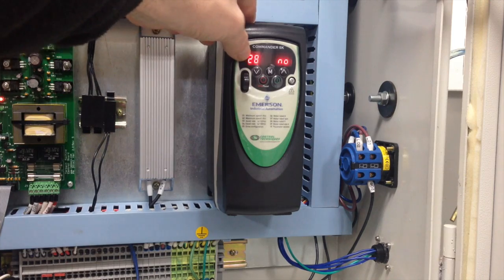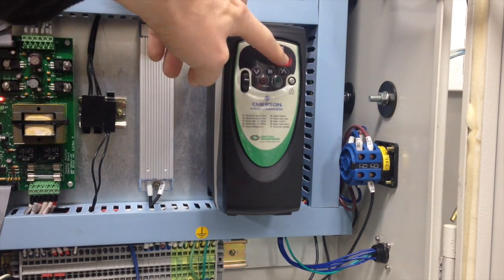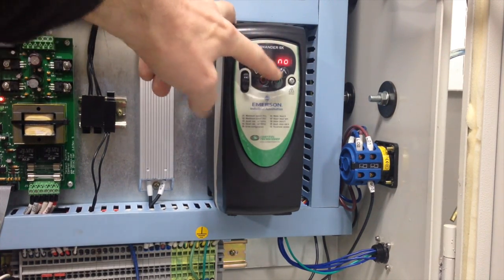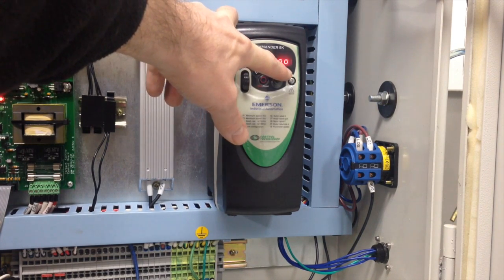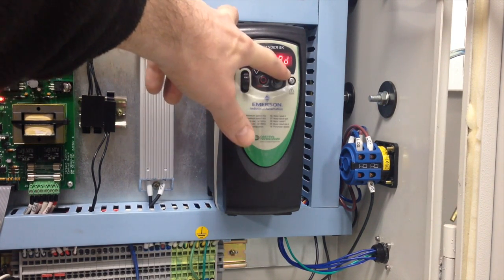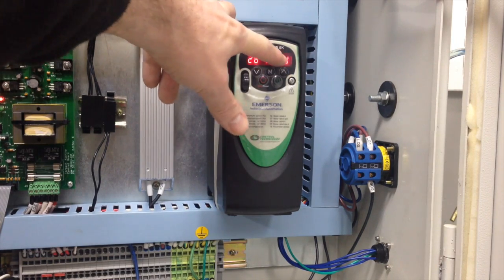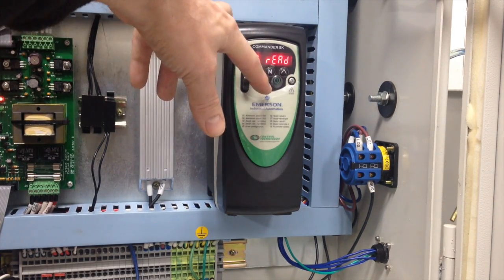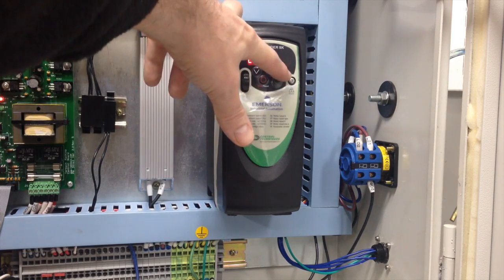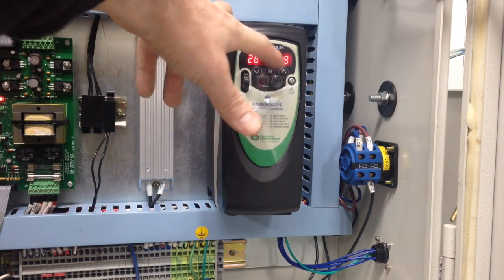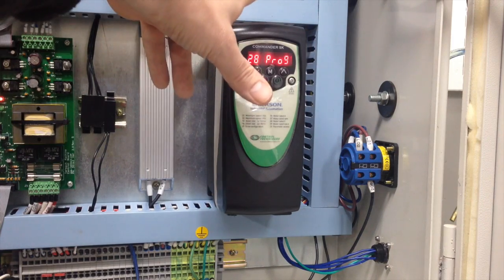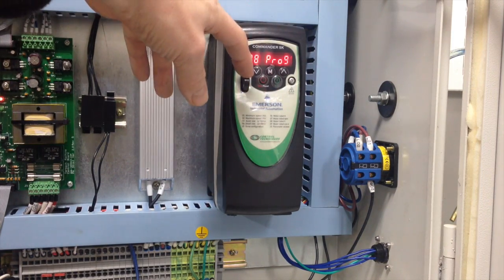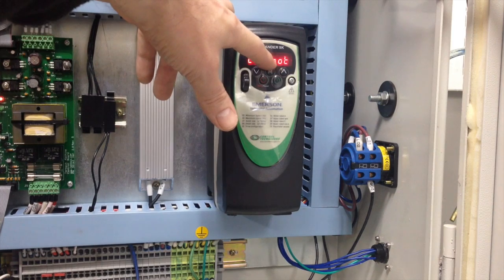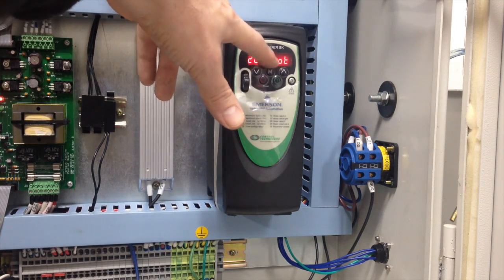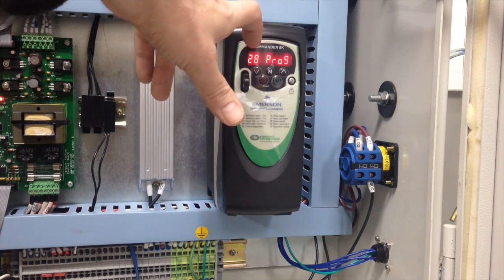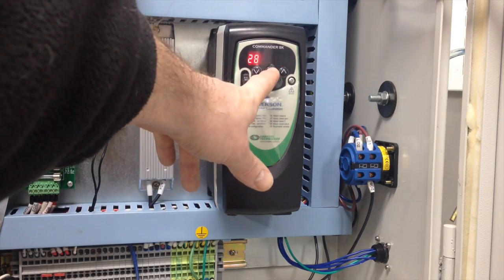And this is the backup parameter. At the moment it's reading no. If you hit M again, you get to change this now. And there are four options. No, read. This basically reads the contents of the stick and programs it to the memory on the VFD. You don't want that. The second one is program mode. That will take the parameters that are on the VFD and write it to the stick. And then the third one is a boot mode. And I'll mention something about that in a moment. But set it to program mode and then just hit the M button.